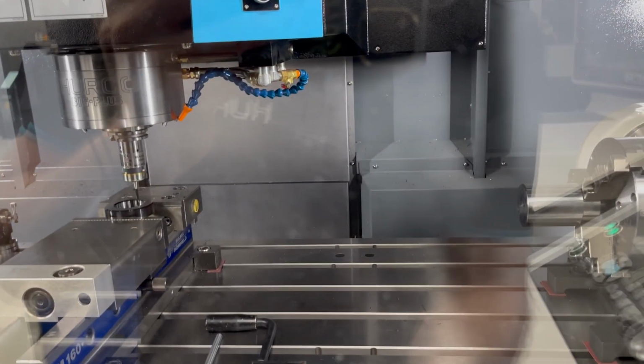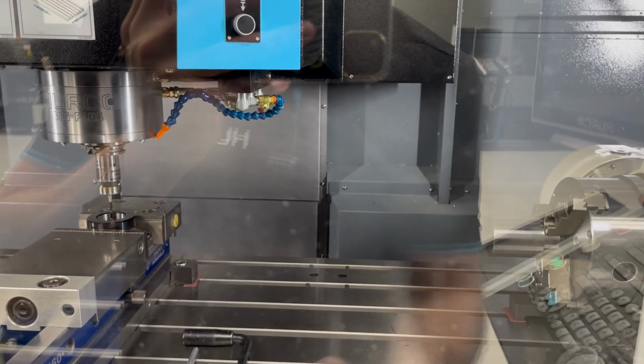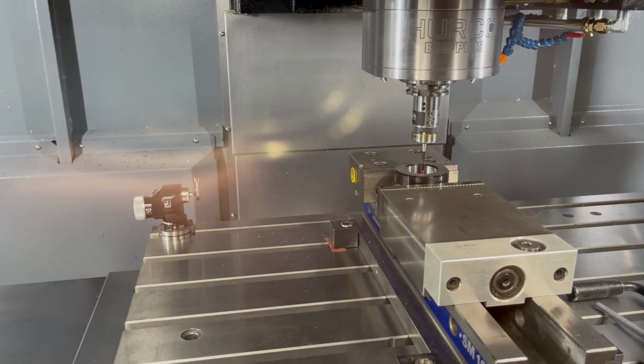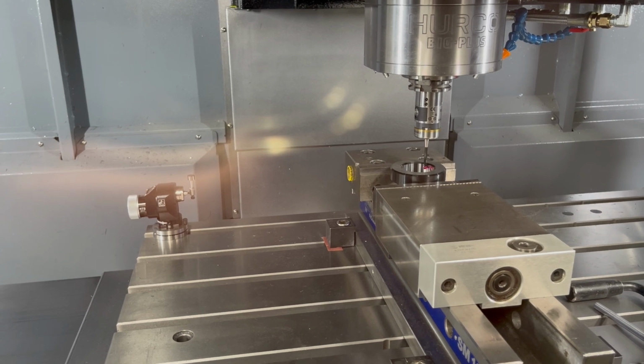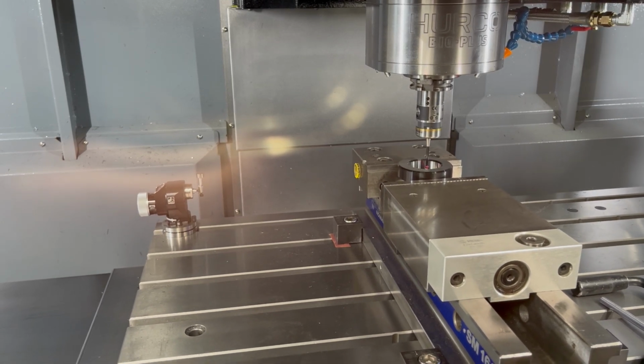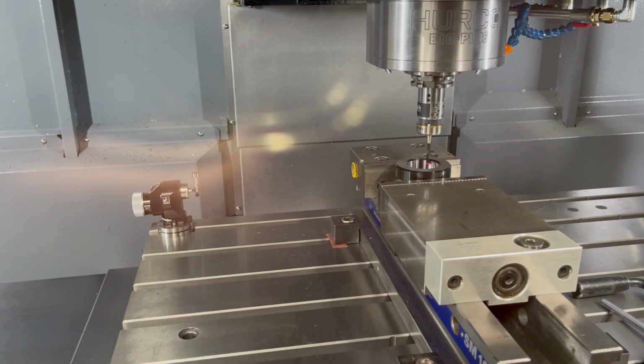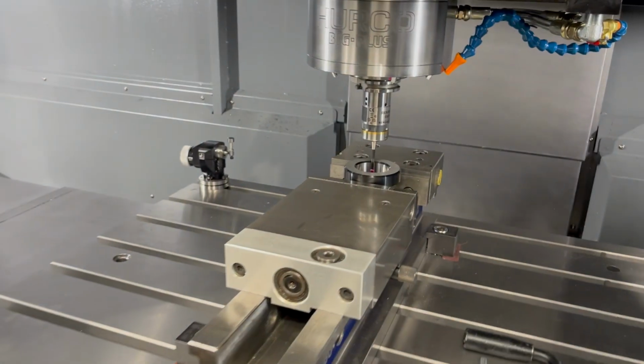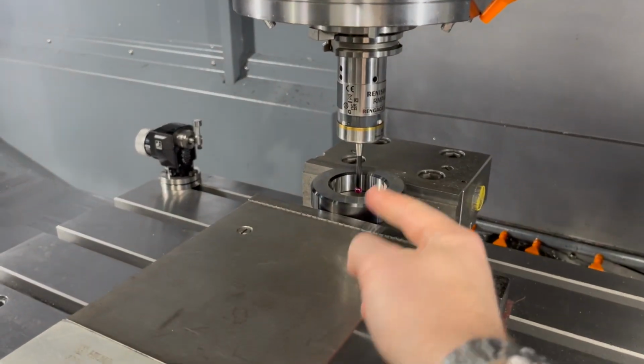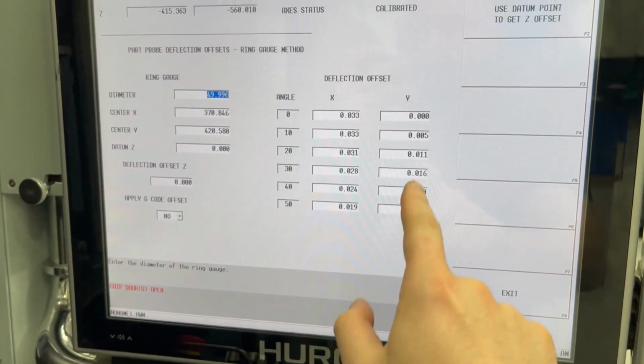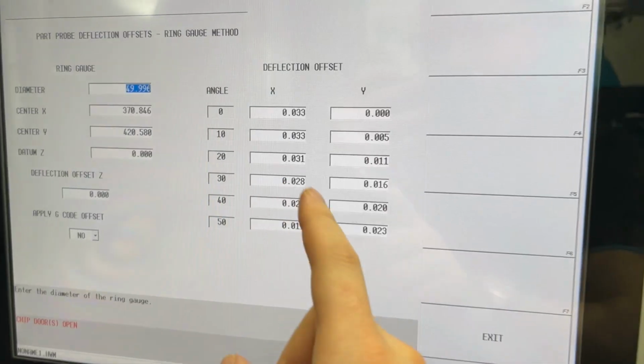Then it will go round, I think it goes round in 36 places, so it'll go around 360 degrees, so that will touch around every 10 degrees, and it might do that twice, I can't remember, but basically what it's doing is it's working out the deflection offsets for the probes. It's basically just working out where it is to where it should be, and it will populate all those figures on the right hand side. So all of those figures that we changed to 0, it's repopulated all those.